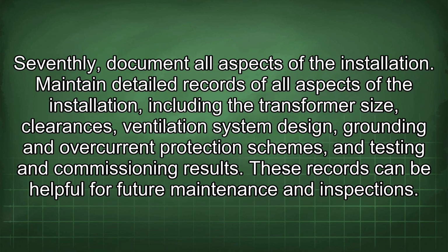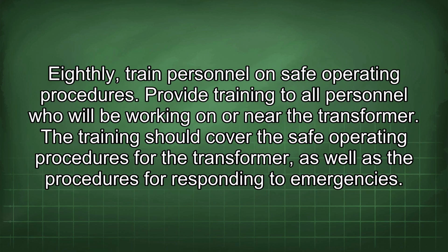Seventhly, document all aspects of the installation. Maintain detailed records of all aspects of the installation, including the transformer size, clearances, ventilation system design, grounding and overcurrent protection schemes, and testing and commissioning results. These records can be helpful for future maintenance and inspections. Eighthly, train personnel on safe operating procedures. Provide training to all personnel who will be working on or near the transformer. The training should cover the safe operating procedures for the transformer, as well as the procedures for responding to emergencies.